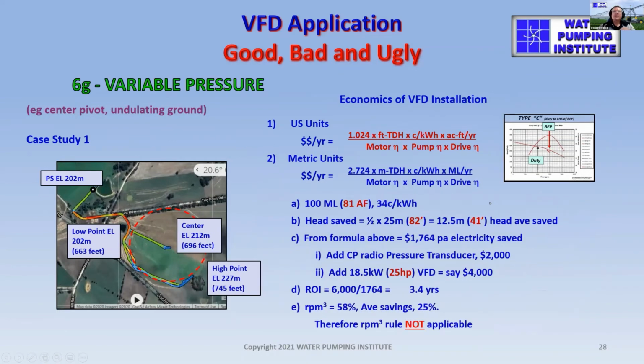So here's a bit of a summary of that potential savings from a center pivot with a remote pressure transducer telemetered back to the VFD. So in this particular case, we're delivering, say, 81 acre feet at 34 cents a kilowatt hour. The head saved is half of the difference between the highest point and the lowest point. The highest point is 745, the lowest point is 663, and that is a distance of 82 feet.